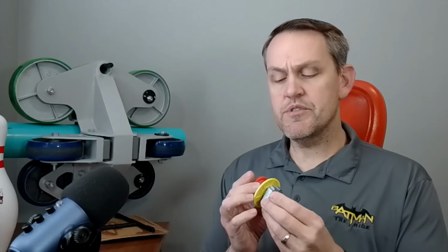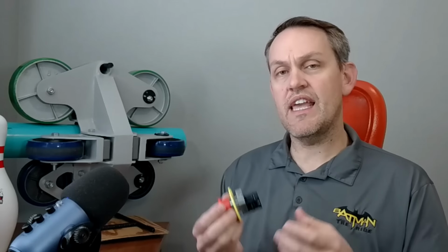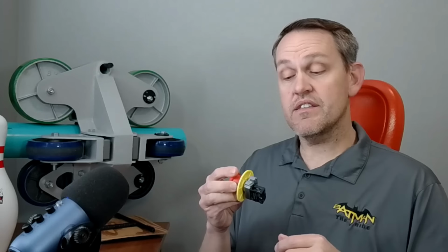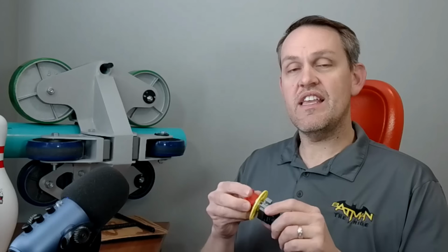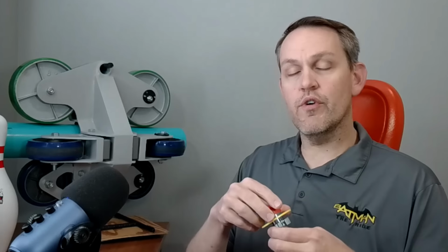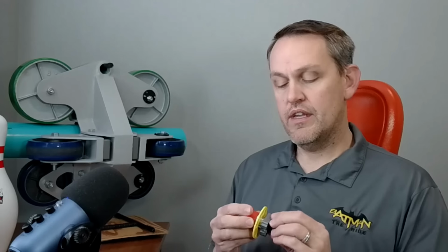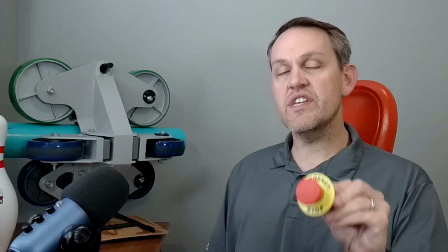Now the way e-stop circuits are set up, they're set up to mechanically interrupt power to almost everything. So controllers and things like that, if you've got a big motor that's running 3 phases through a big contactor, you have a little control voltage wire that runs into that contactor that makes it hold down. And when you hit that e-stop, it interrupts that control voltage, opens the big contactor so the big motor can't move.